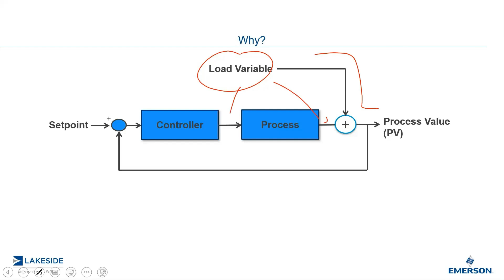The most common application for feed-forward control is in boilers. Feed water comes in under cascade control from a level controller, and steam is generated. But this is a load variable: every time there's a disturbance in steam, it affects the level and changes the flow. So if we understand that relationship, every time there's a change here, maybe we should proactively make a change there.